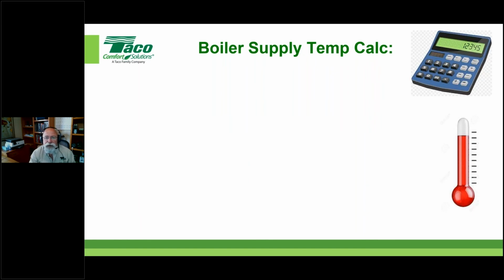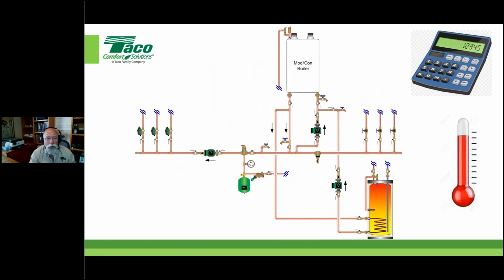That boiler supply temperature, this is a review. We've done this before with you. This is just showing you if I had a 140-degree temperature going out to the system and I designed it at a 20-degree delta T, that shows me my delta T across the system. The question is, what should I set the boiler up for so that I get this 140-degree out here when I actually have a blending happening here? It's actually higher than 140. How do we know how to figure out what it is?